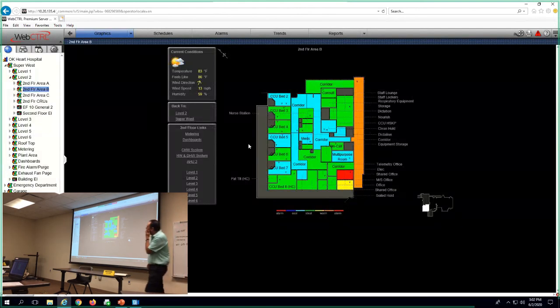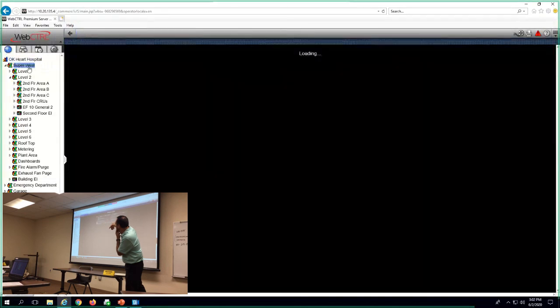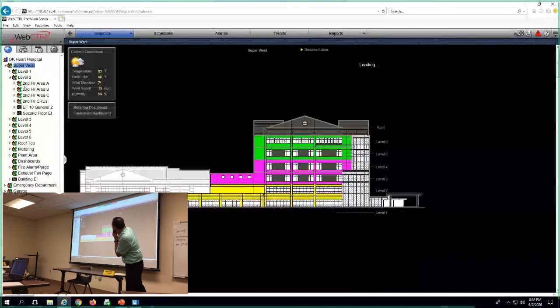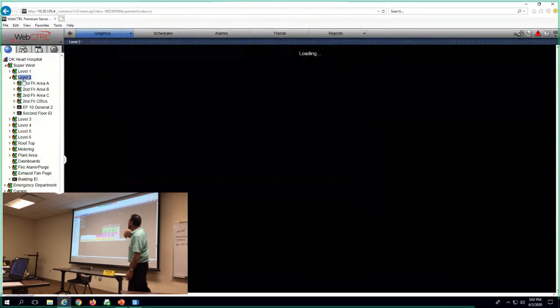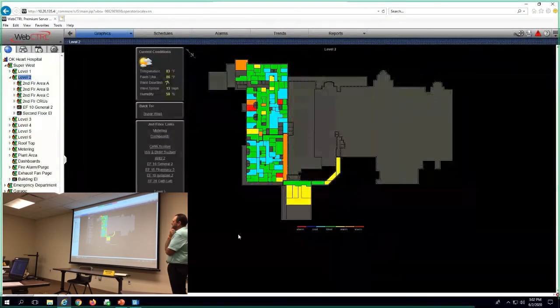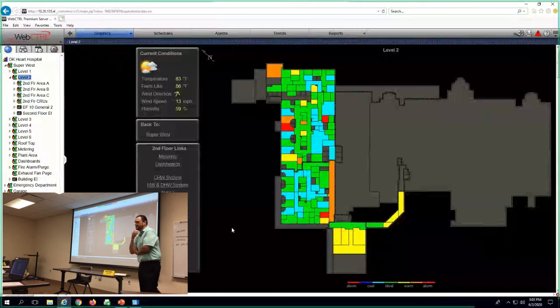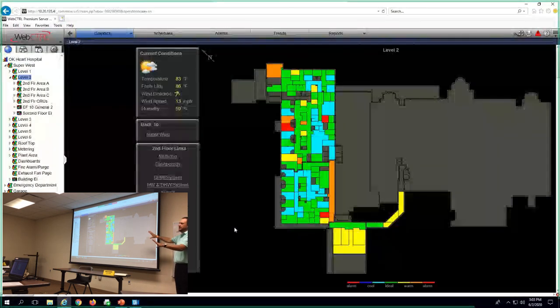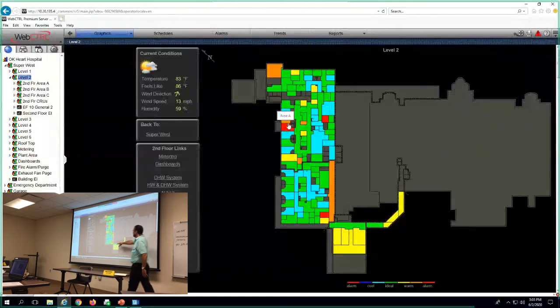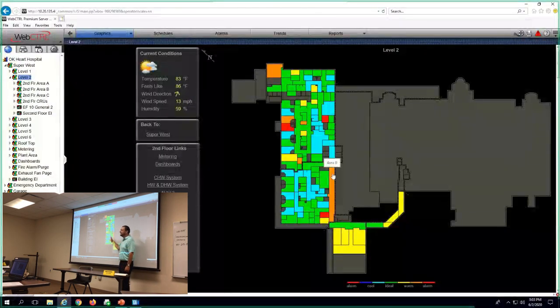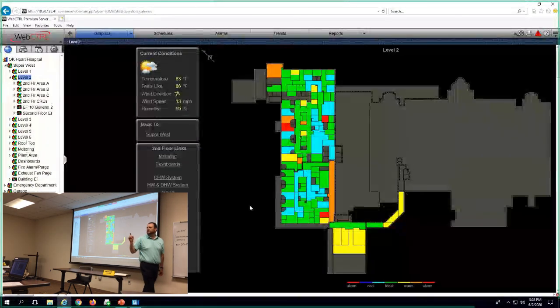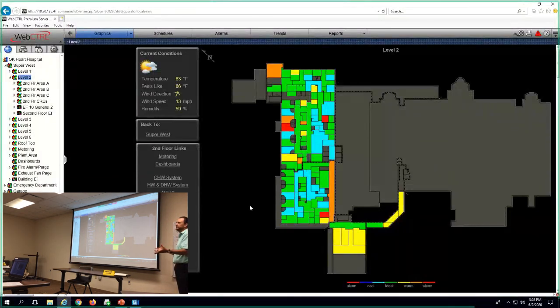So you can look at, click on, up there at Super West. Not the Heart Hospital. No, that's not it. Go down to level 2. Well, just click on level 2, the whole second floor. So right now I think there's like 60-something zones on that floor, at least 60-something VAVs or so. In one snapshot, I can tell you where the problems are, where the VAVs that are not tracking to the set points are. It's these red ones, the orange ones, and if we have any dark blue ones, they're not tracking set point. There's something wrong in those spaces that we need to go investigate and see what's going on, because they're not tracking the set point.